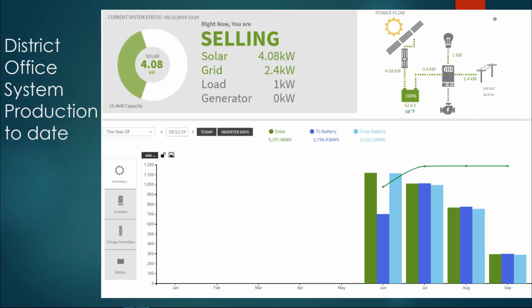We've been in discussions a bit with Kit Carson Electric Co-op. They're wanting to potentially install some control over the storage so they could maybe obtain some benefit from the storage system. We're already providing some benefit to their system since we're at the end of that 15 kV line, and when we're backfeeding the grid, even if it's just a few kW, we're helping the power and voltage levels on that line out there—just a volt or two, but still helping a bit on the end of that long radial line.